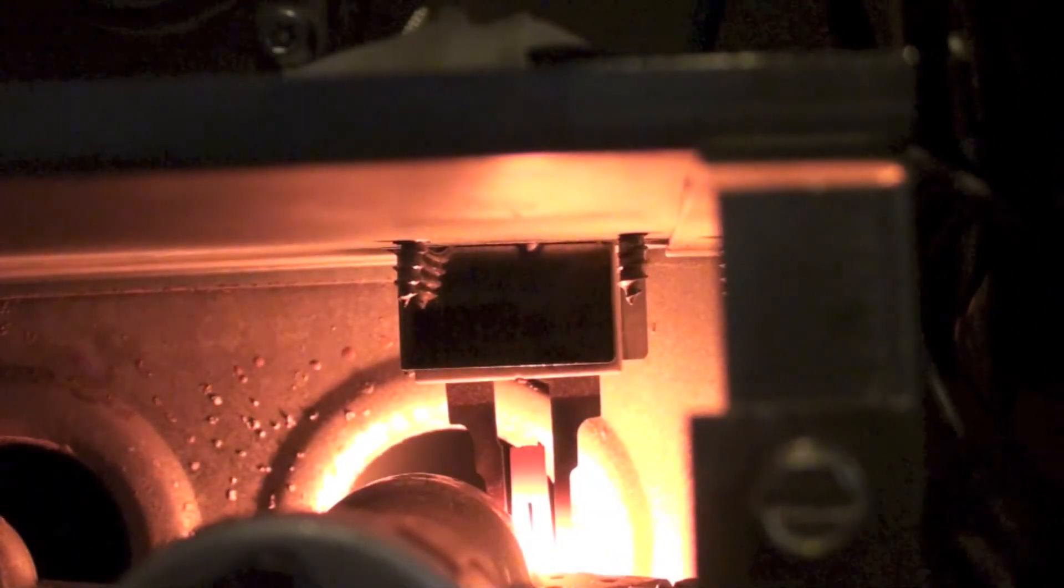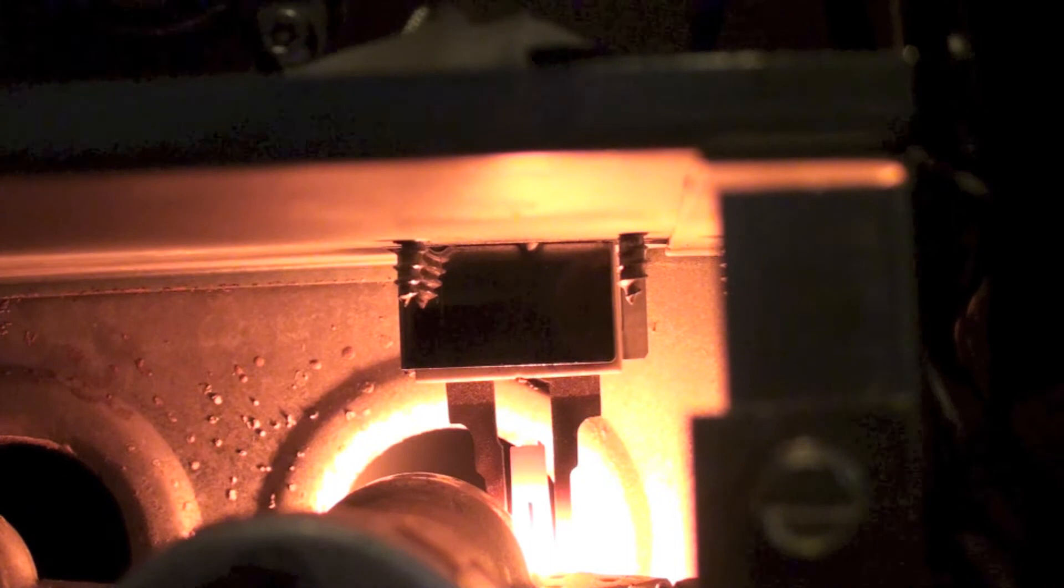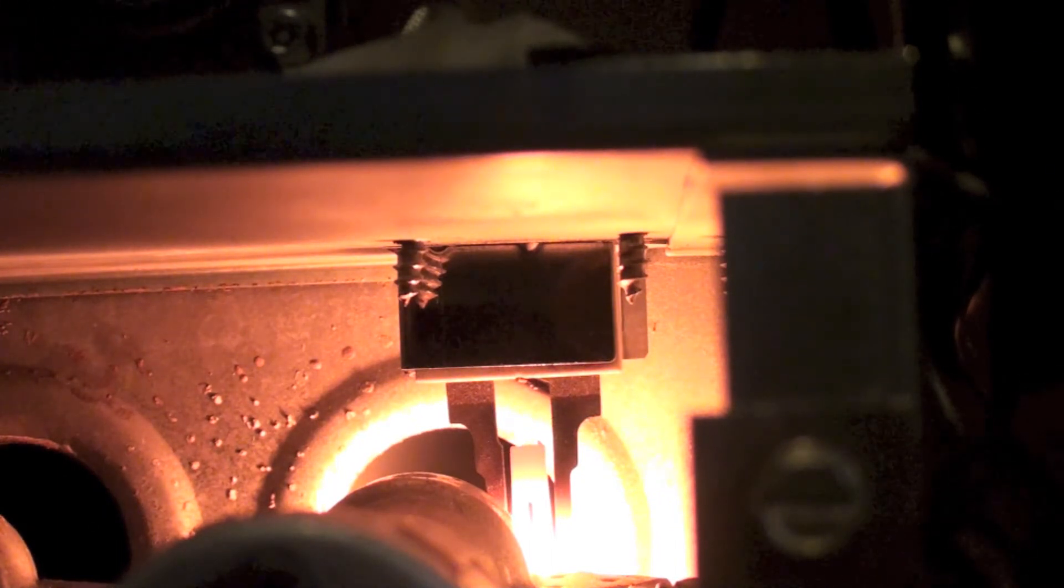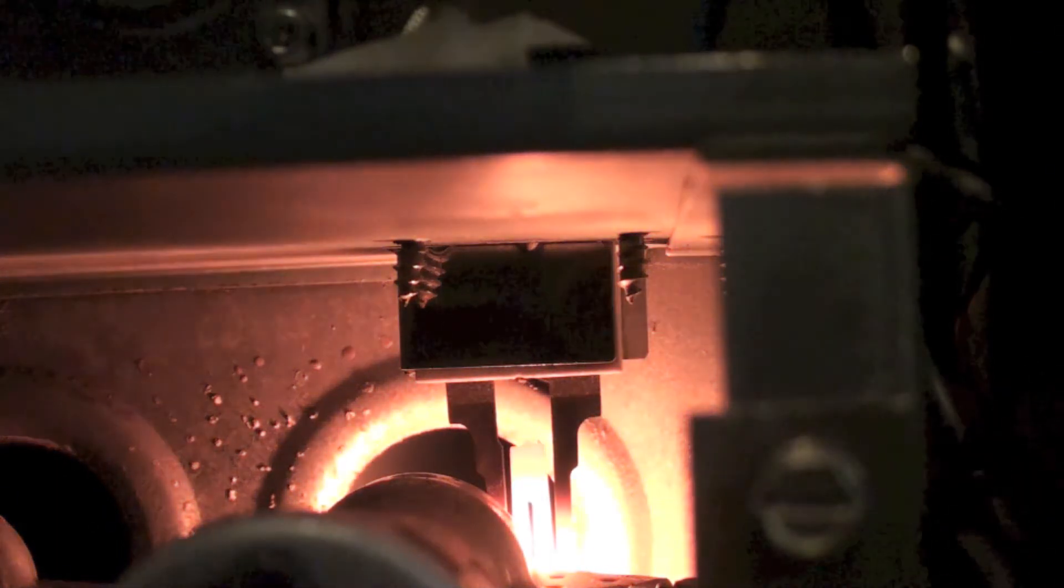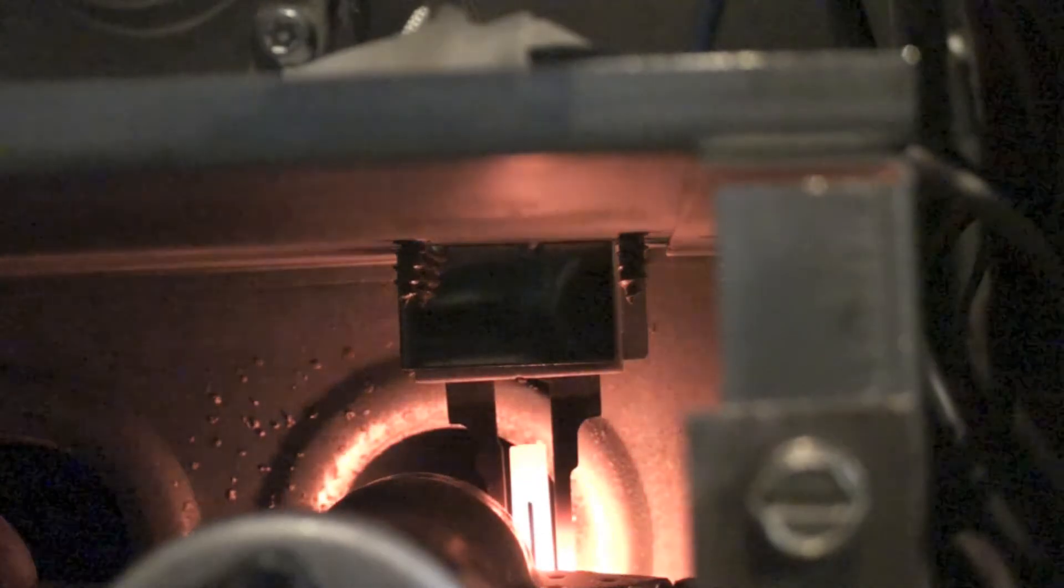Okay, looks like it's pretty well warmed up now. Burners would normally come on. You're looking for white spots in that thing. If there's any real bright yellow spots, then that means it's about ready to fail.